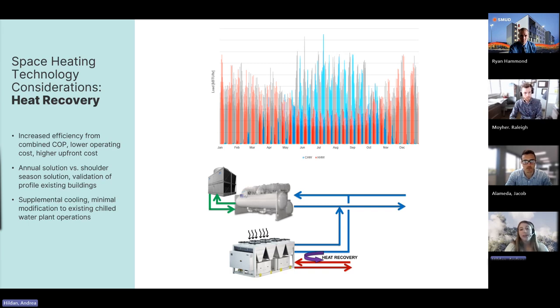And then sometimes with the utility bills not being enough information, we've even considered doing simple energy box models to help build the profile and how we'd anticipate these buildings to operate. Another point I just wanted to illustrate here on the heat recovery slide is not to be dissuaded if you don't have a simultaneous load year-round. A lot of times there's opportunities to take advantage of heat recovery in shoulder seasons alone. So on this graphic here, you can see simultaneous load in the shoulder seasons, which is your early spring, some parts of summer, and then fall.